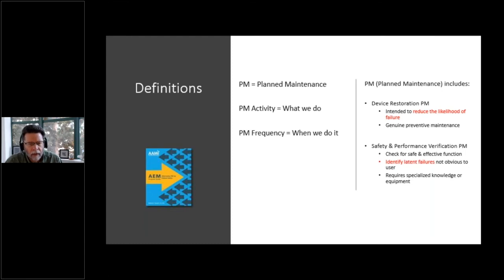So an AEM program, an AEM procedure, lets you adjust either or both of these, activities or frequencies. You could change the kinds of things you do. You could drop a step or change a step, check the defibrillator output at 2 levels instead of 10 levels, as long as you've got data. And or you could change the PM frequency and say, my records show that I don't have to do this twice a year, I could do it once a year, and I'll give that a try. And with good data, you can say, I'm going to make the frequency 0. You can do a run to failure option that says, this otoscope ophthalmoscope unit does not get safer or more reliable because I send an expensive technician around to turn on the light bulb and see if it lights up. So there are things that we can consider, at least dropping them altogether.